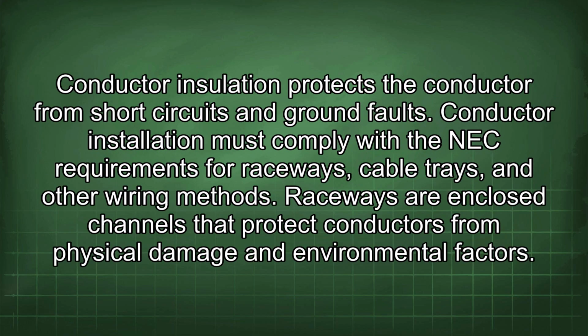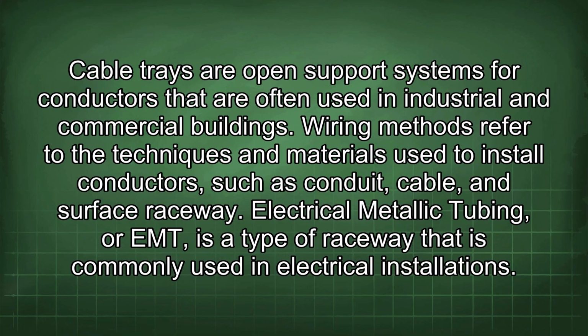Conductor insulation protects the conductor from short circuits and ground faults. Conductor installation must comply with the NEC requirements for raceways, cable trays, and other wiring methods. Raceways are enclosed channels that protect conductors from physical damage and environmental factors. Cable trays are open support systems for conductors that are often used in industrial and commercial buildings.